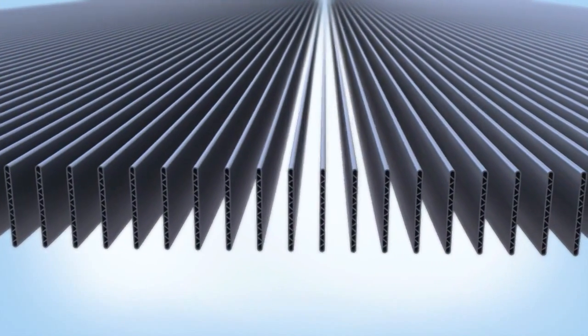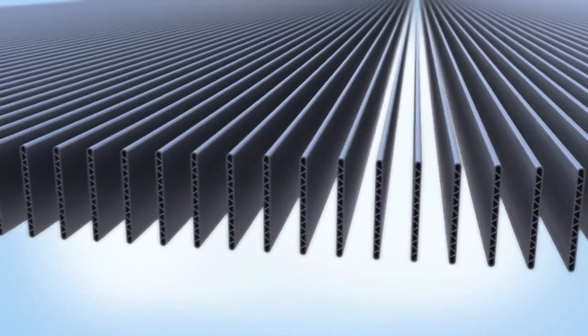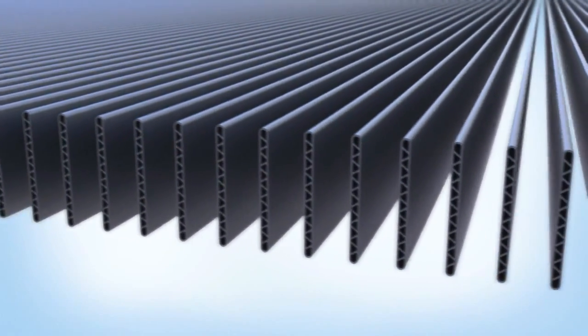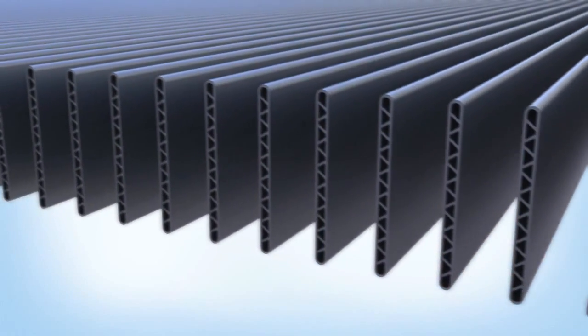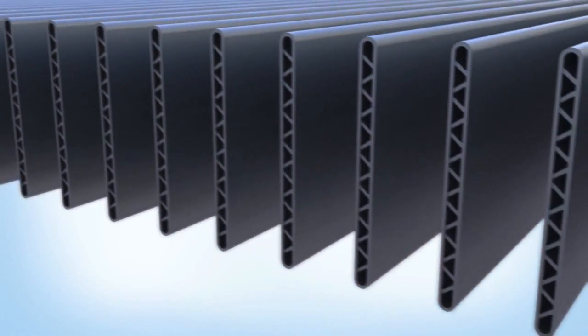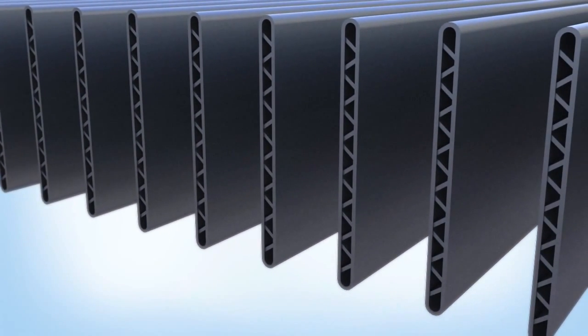This is primarily achieved through an innovative new micro-channel coil design that provides over a 70% reduction in condenser refrigerant charge compared to traditional round tube plate fin condensers.